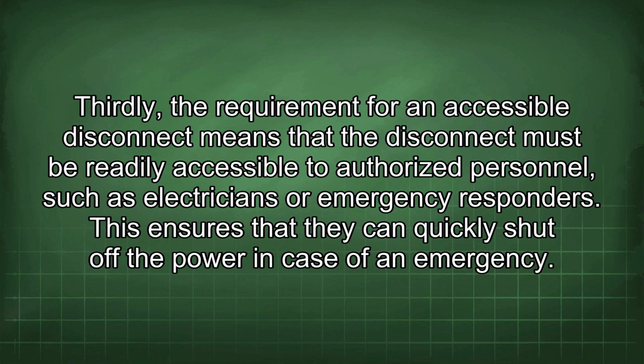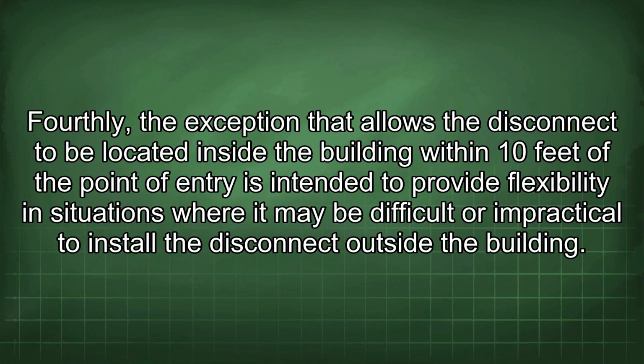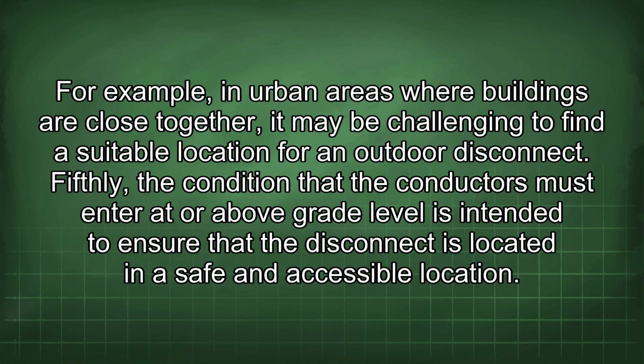Thirdly, the requirement for an accessible disconnect means that the disconnect must be readily accessible to authorized personnel, such as electricians or emergency responders. This ensures that they can quickly shut off the power in case of an emergency. Fourthly, the exception that allows the disconnect to be located inside the building within 10 feet of the point of entry is intended to provide flexibility in situations where it may be difficult or impractical to install the disconnect outside the building. For example, in urban areas where buildings are close together, it may be challenging to find a suitable location for an outdoor disconnect.